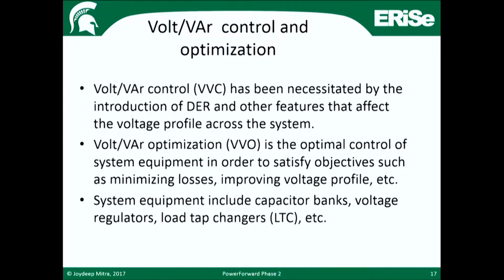Very briefly now, coming to Volt-VAR control, what it is: the need to control voltage and reactive power. VAR stands for volt-amperes reactive. Reactive power is power that doesn't really consume energy as such, but it's out there. There are components that suck up reactive power, and you have to make sure there's enough of it, otherwise nasty things happen to the system. And you have to make sure there's enough voltage available to meet safety and standard requirements.